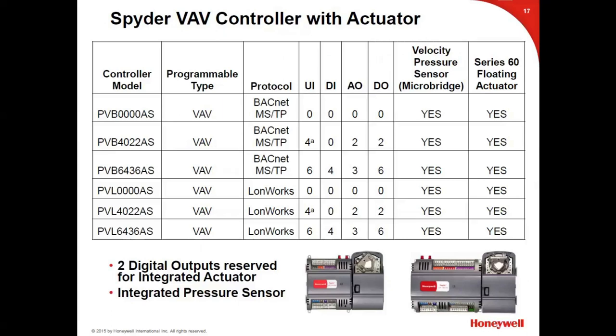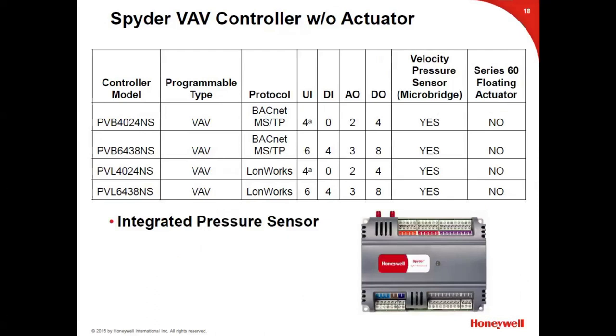Here are the VAV controllers — BACnet and LON — shown on one chart. The part number naming convention: 'P' means programmable; the second character is either 'U' for unitary or 'V' for VAV; the third character is 'L' for LON or 'B' for BACnet. The four digits after the letters identify the I/O: universal inputs, digital inputs, analog outputs, and digital outputs. For example, PVB-4022-AS has four universal inputs, zero digital inputs, two analog outputs, two digital outputs, an airflow pickup sensor, and an actuator ('A'). 'N' means no actuator.